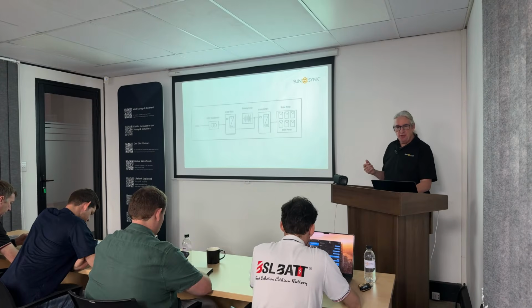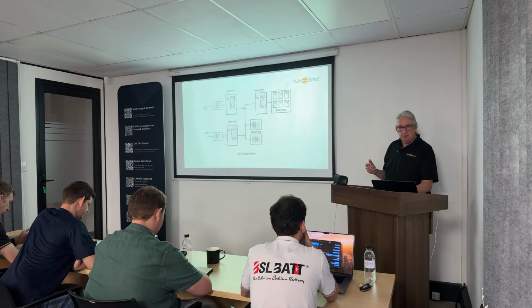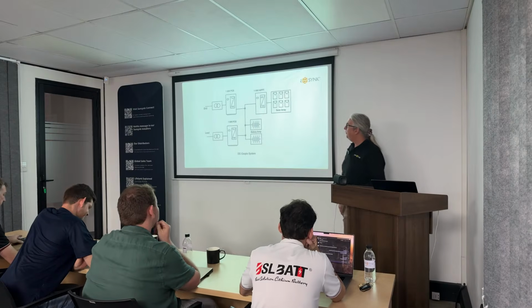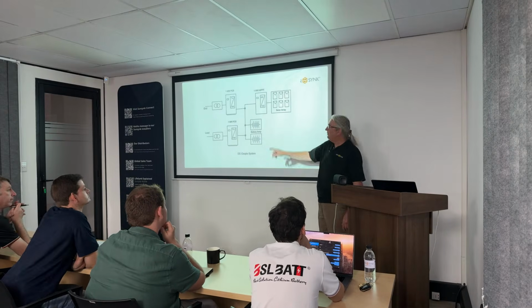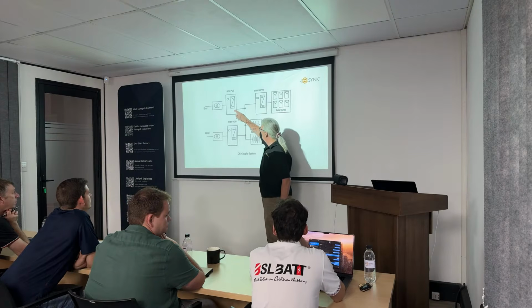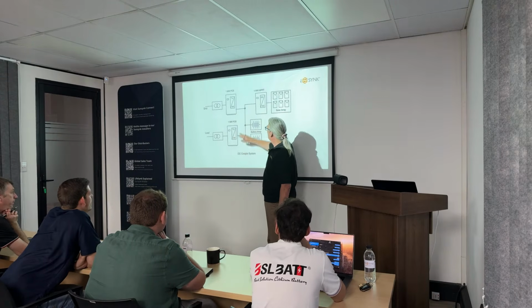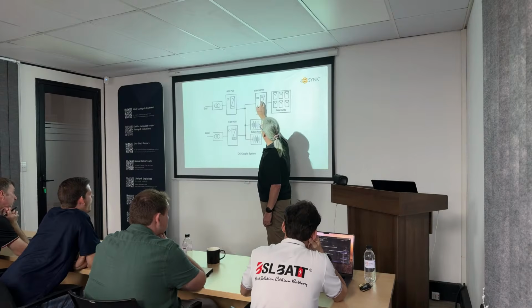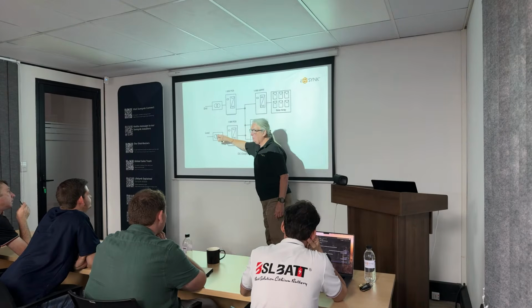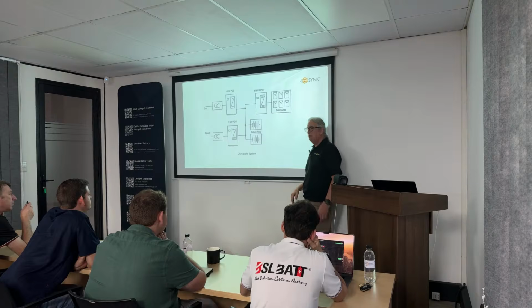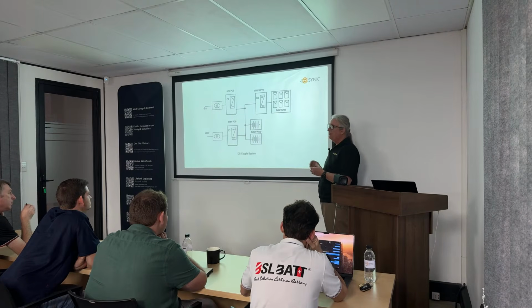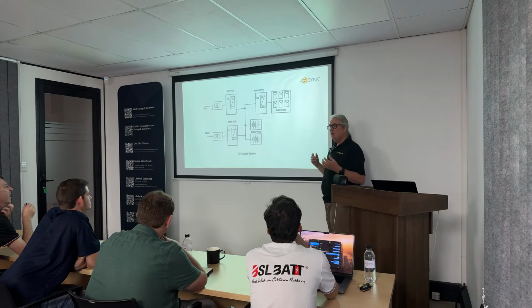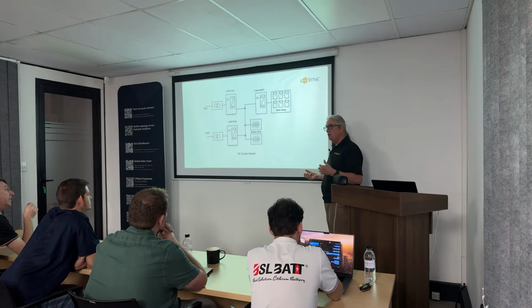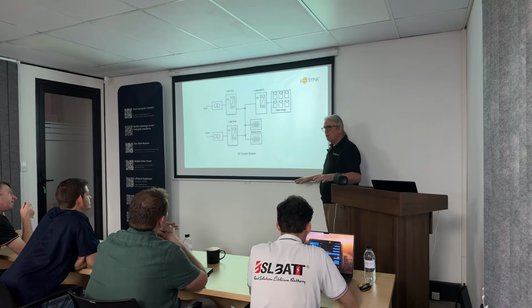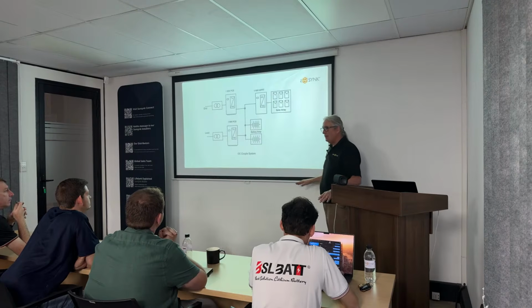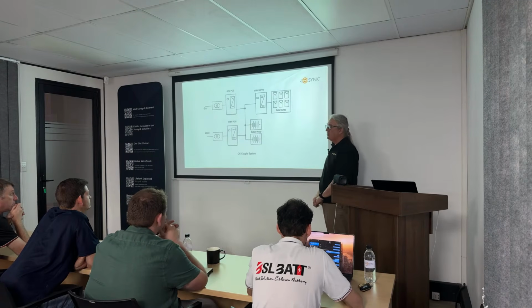One of the configurations is quite interesting. This one is using a DC coupled. So it's where you have your PCS here, and you've got another PCS here. And so it comes in, it will charge the batteries, any solar will come in here, and it will output through the PCS onto the load. It completely isolates. So if you've got a very noisy grid, or if your grid cannot always supply the peak demand of the load, or if you cannot afford any risk at all, any interruption, zero interruption, nothing, this sort of configuration is quite nice.